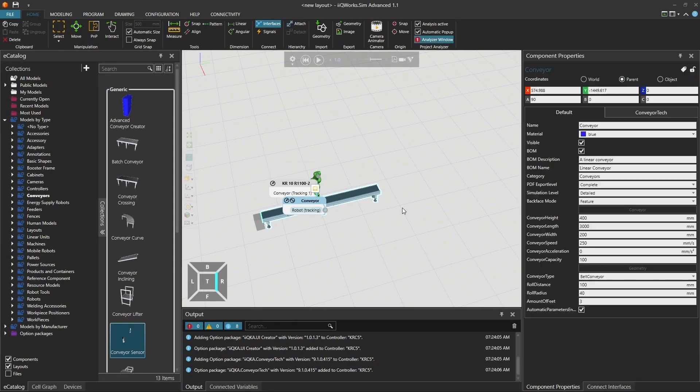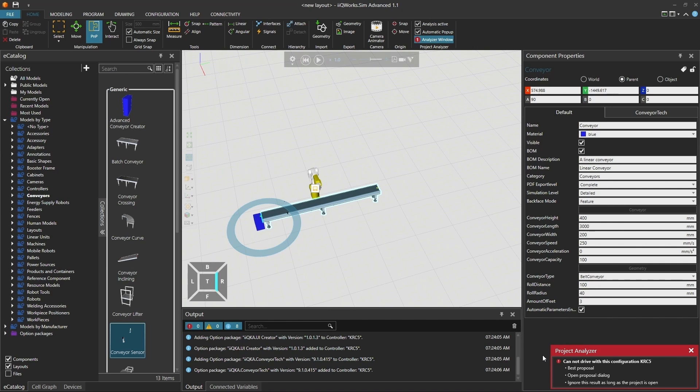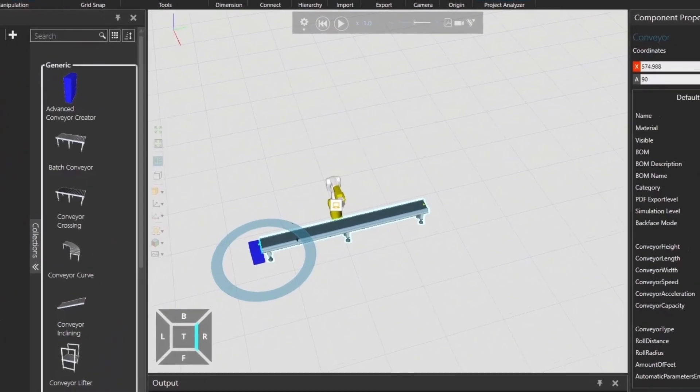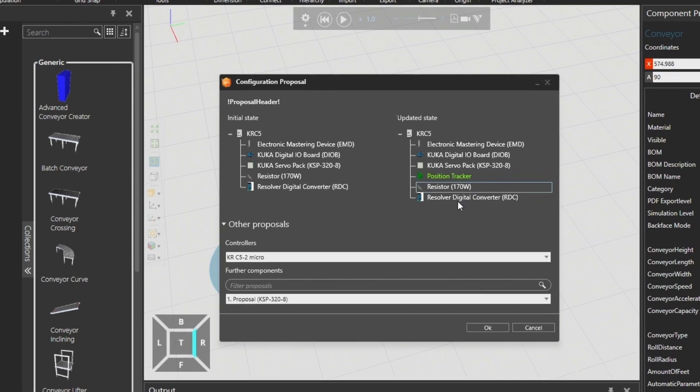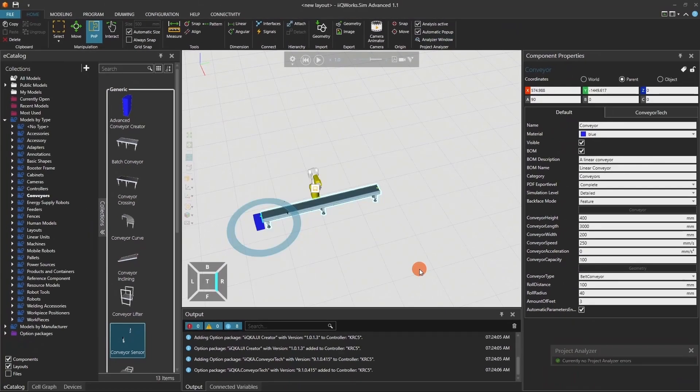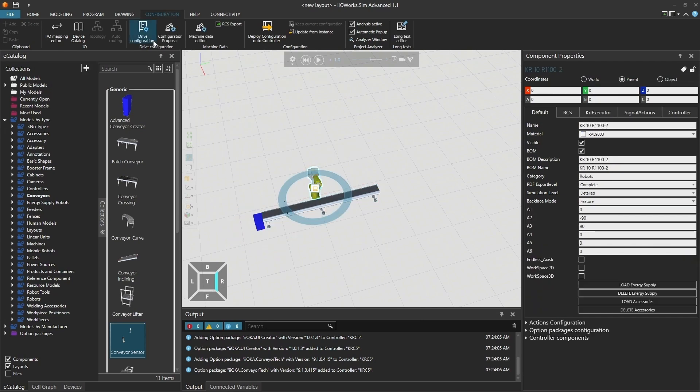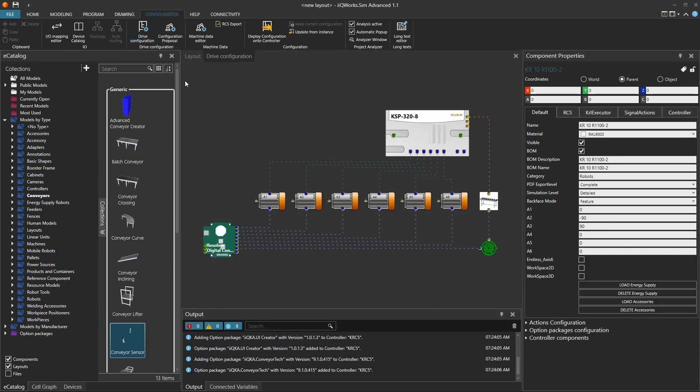Let's continue by configuring the RDC if you selected it as your position interface. After selecting the RDC, the Project Analyzer will notify you that your standard configuration is missing a position tracker. Click on Open Proposal dialog. A new configuration proposal window will open. In the updated state, a position tracker will be automatically added. Click OK to proceed or adapt the configuration to match your real hardware setup. To validate the configuration, go to the Drive Configuration tab. You should now see the position tracker listed.